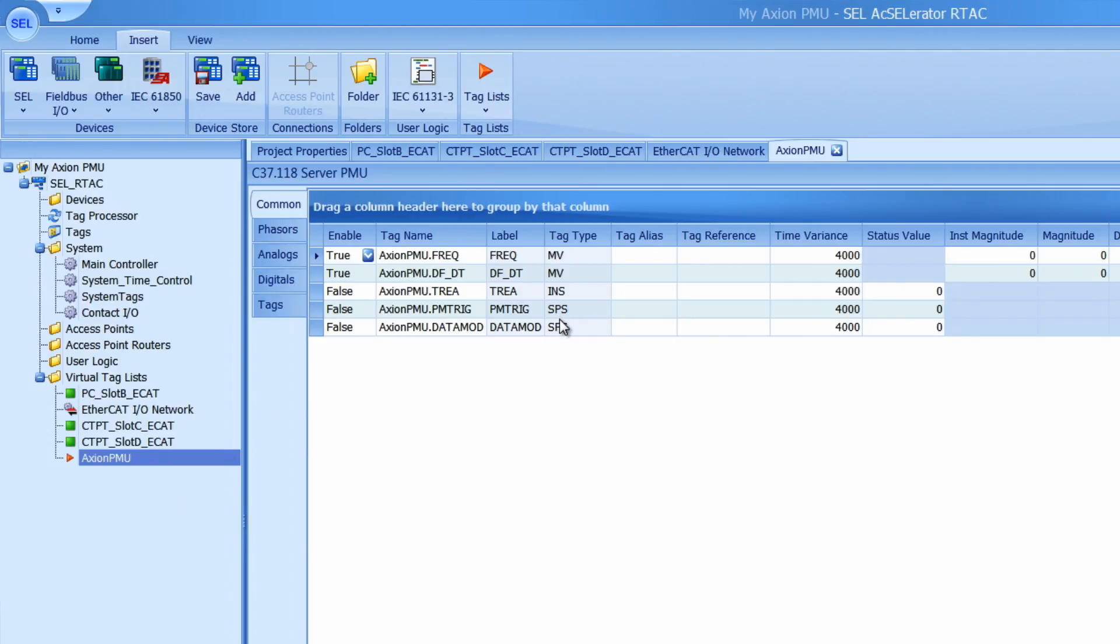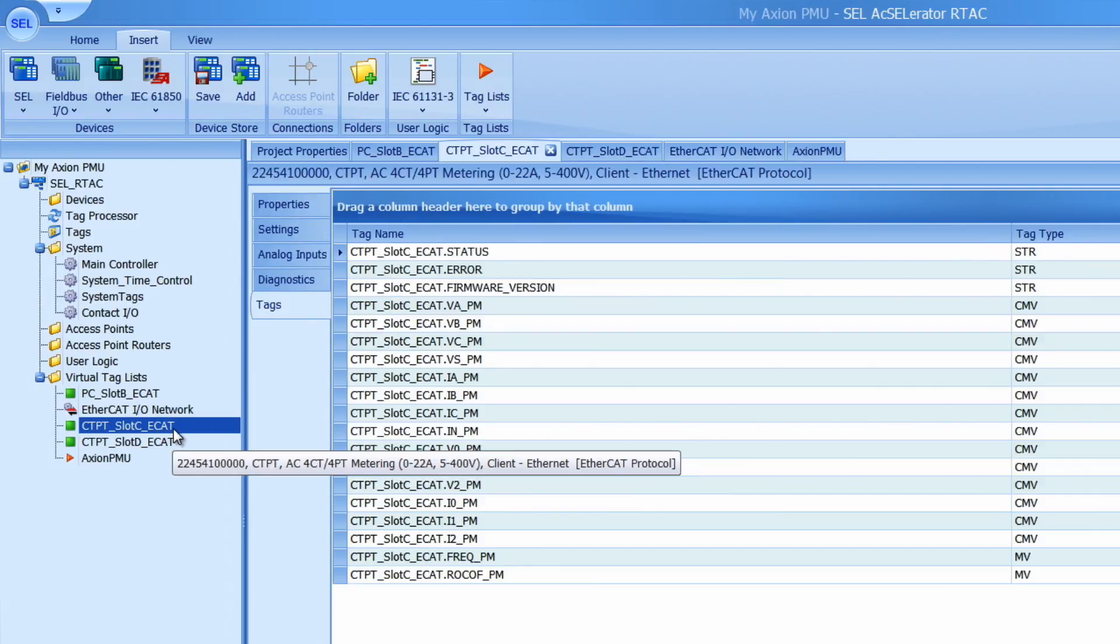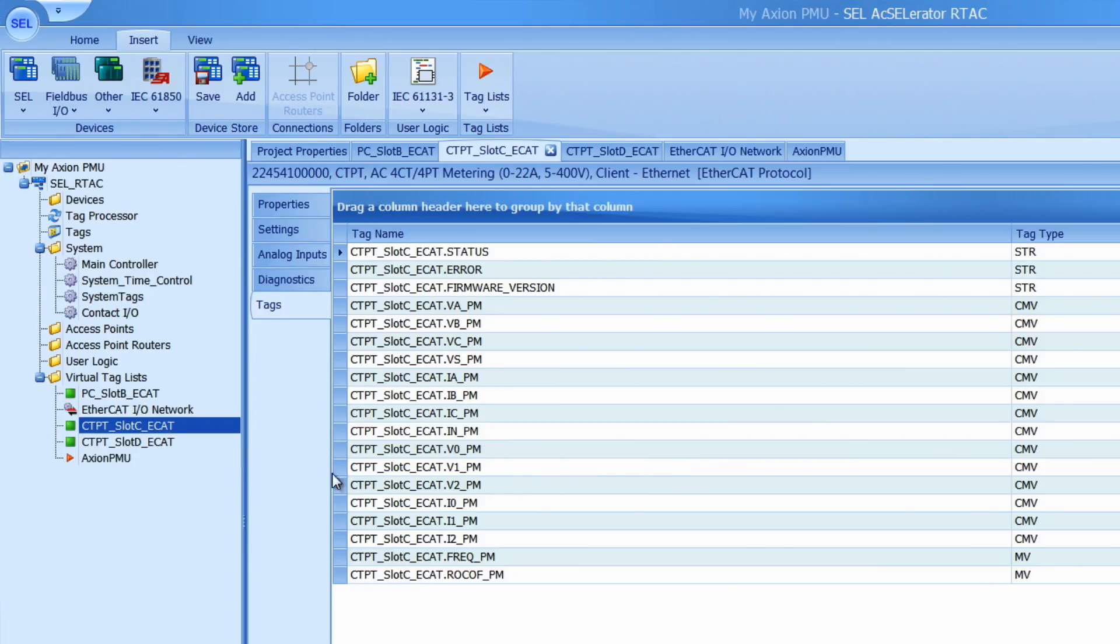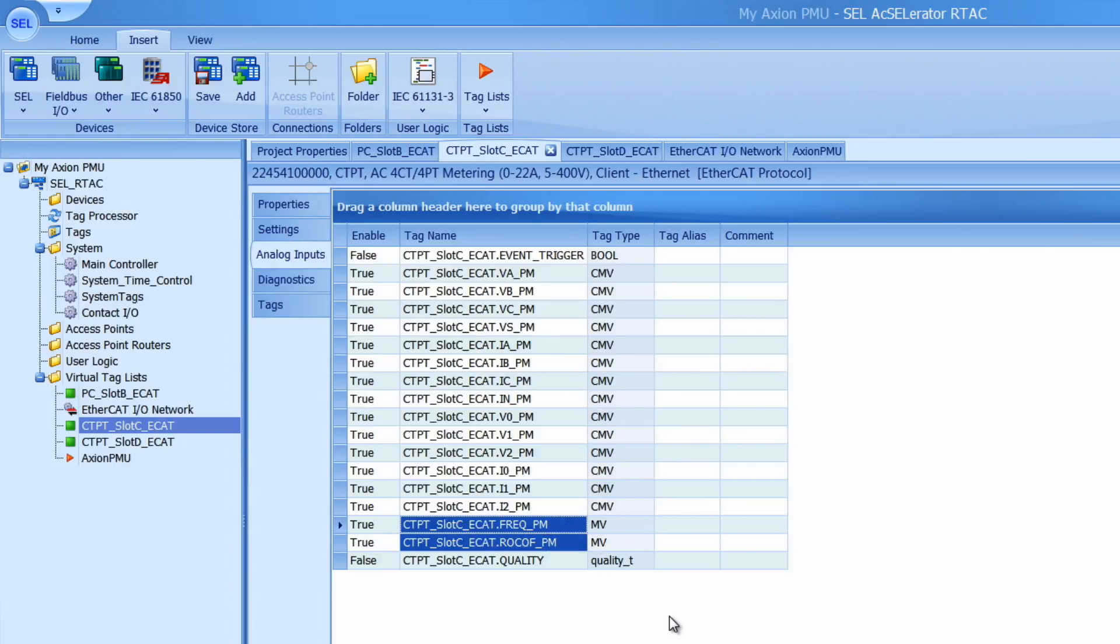So the virtual tag list requires a frequency component inside of the tag list. To add in a frequency quantity I will select one of my CTPT modules as the frequency reference. I will select on the CTPT modules in slot C and go to the analog inputs and find the frequency tag. And just for fun I'm going to use the rate of change frequency tag as well. This ROCOF frequency. Highlight over those hit control C.